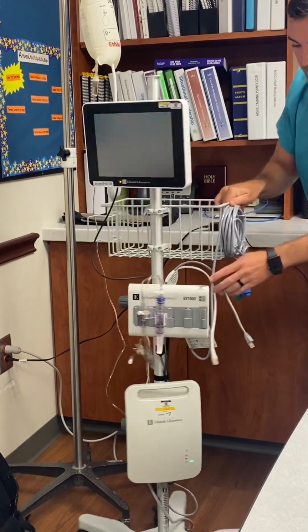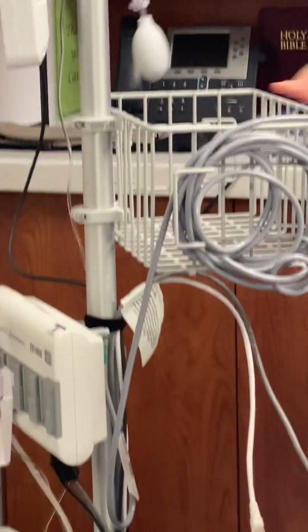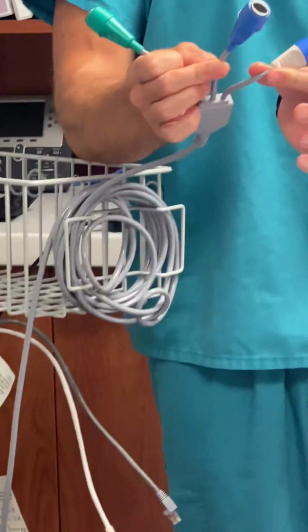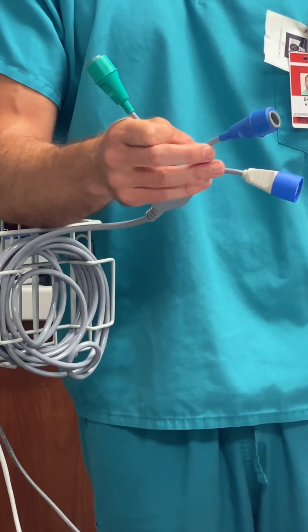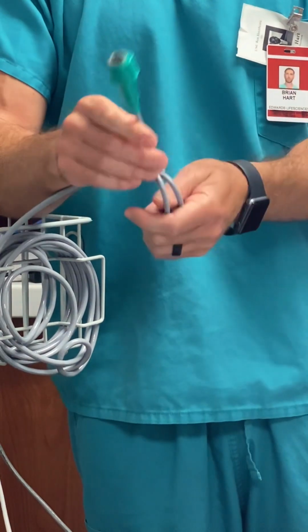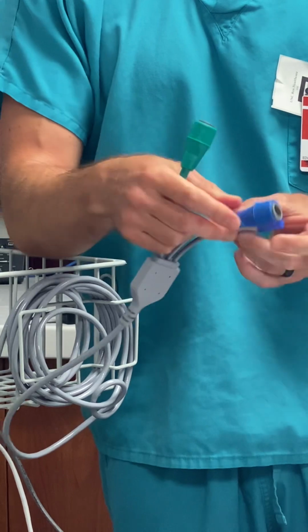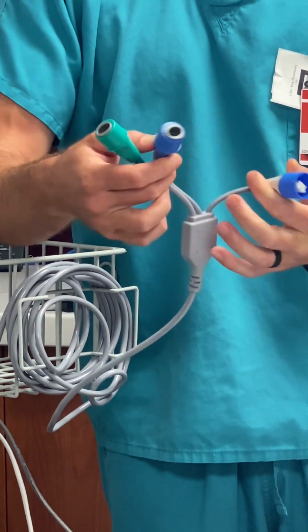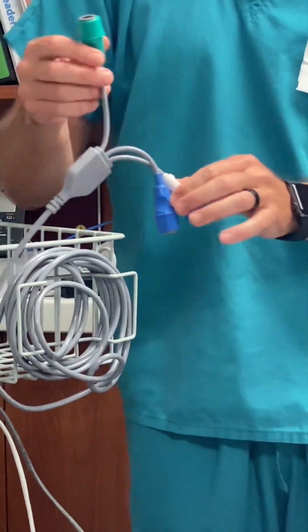So over here in the back of this data box is this cable right here, and you can see there's 3 pigtails. These 2 are to transduce a CVP. You don't need to do that. You can just hook up your CVP how you normally do. The only one you need to be concerned about is the green cable, and you can just leave these just how they are. You don't have to put them together like that because it'll actually cause an error.